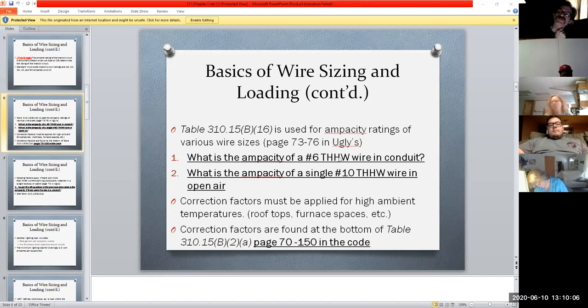There are exceptions where you might have a different kind of insulation depending on the environment it's meant to go into. But very commonly, THHW is meant for things on the outside, if you have outlets outside that you're delivering to. Within the house, typically it's THHN. But we could go into the Ugly's book and look. If I were to ask you, what's the ampacity of number 6 THHW wire in conduit? It would have a rating to that. We could look and see what's the ampacity for a single number 10 THHW wire in open air. Again, it's a temperature factor you're dealing with. If it's in conduit, that's one factor. If it's just running in open air, that's an entirely other factor.